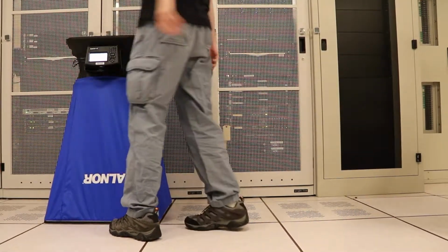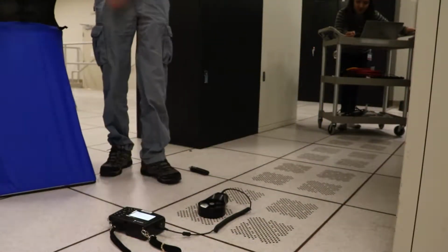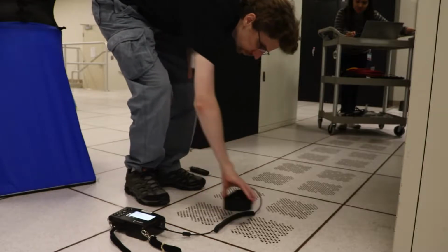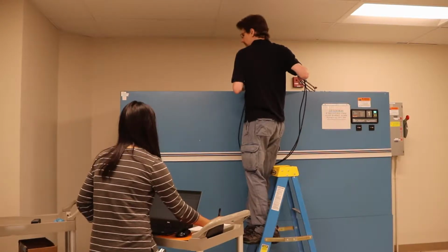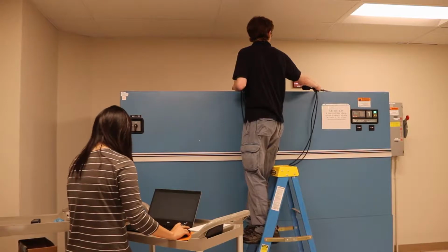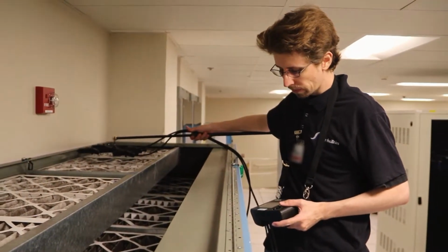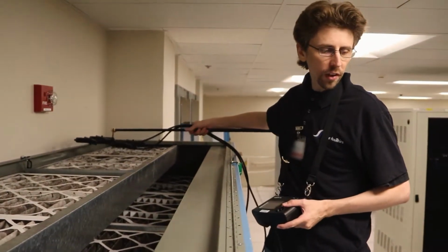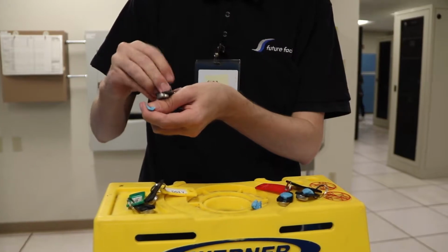Flow rate is measured for every accessible grill, using proprietary methods, one of which uses a flow hood in conjunction with a vane anemometer. We are able to accurately record grill flows for any raised floor. Using a flow measurement matrix, air velocity is measured across the return of a CRAC. The velocity measurements from all CRACs are compared to establish relative flow rates, which are later scaled to match room load. Temperature sensors are placed on the supply and return of each CRAC.